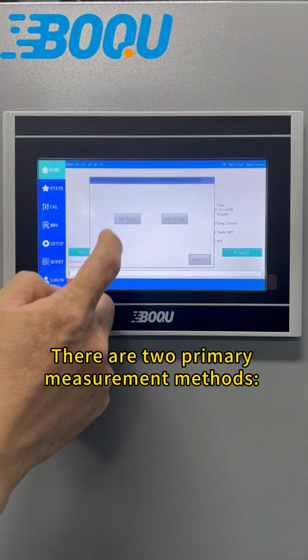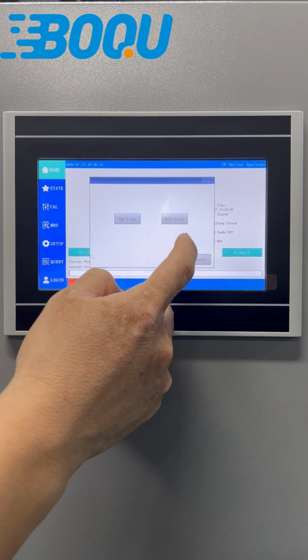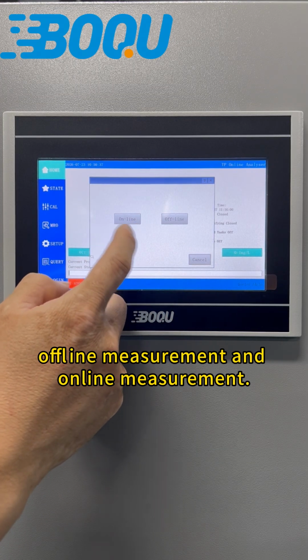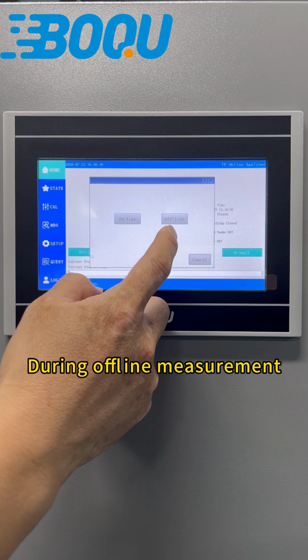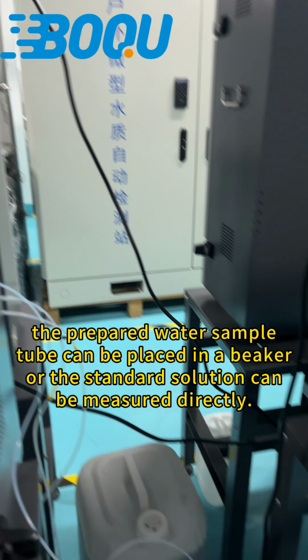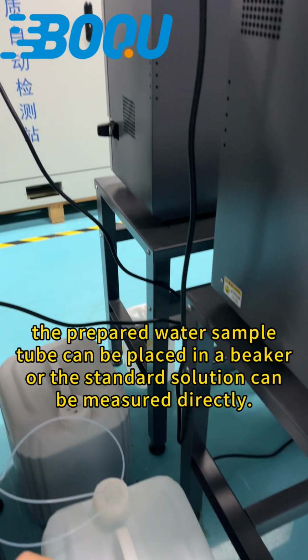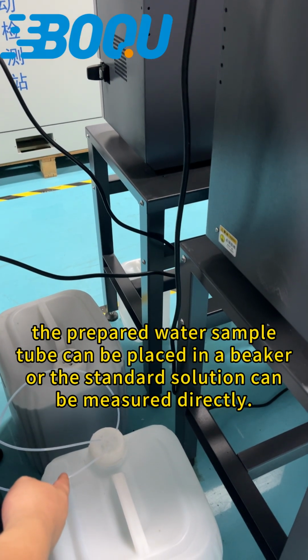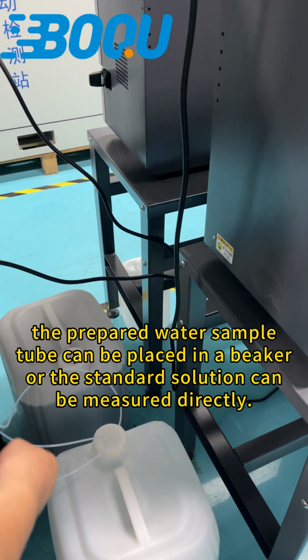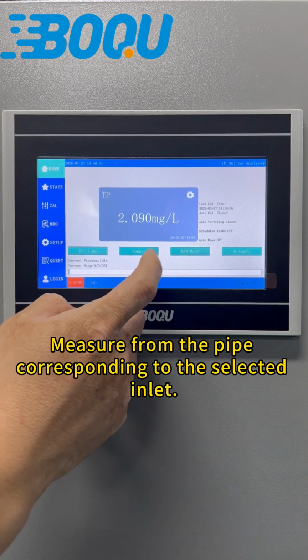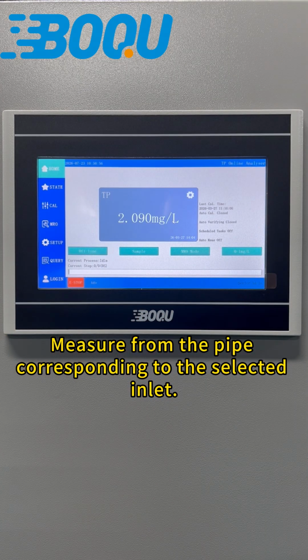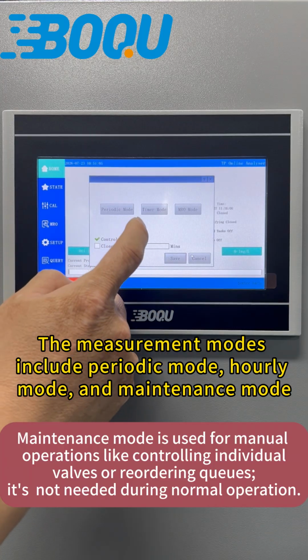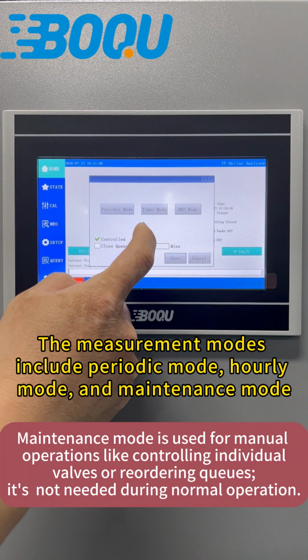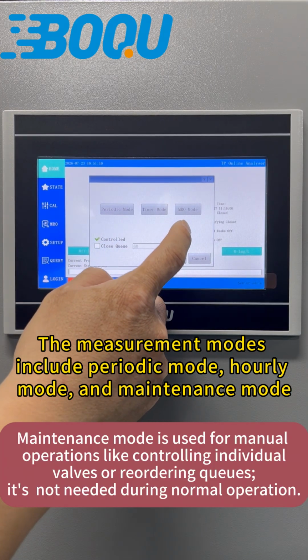There are two primary measurement methods: offline measurement and online measurement. During offline measurement, the prepared water sample tube can be placed in a beaker, or the standard solution can be measured directly. Measure from the pipe corresponding to the selected inlet. The measurement modes include periodic mode, hourly mode, and the maintenance mode.